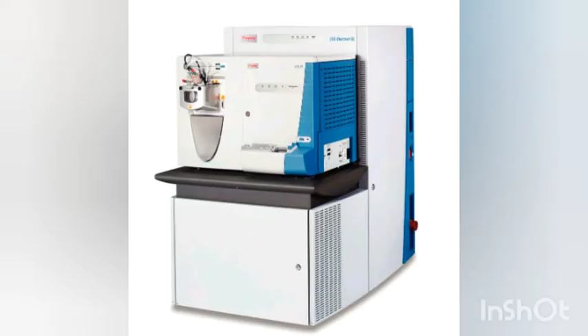Hybrid linear ion trap Orbitrap mass spectrometry. The hybrid linear trap Orbitrap MS, which combines a linear ion trap and a high resolution Orbitrap, is one of the tandem mass spectrometers. The LIT uses a set of quadrupole rods to confine ions radially and a static electrical potential on the end electrodes to confine the ions axially. The Orbitrap consists of an axially symmetrical mass analyzer and makes ions move in an orbital motion around the spindle. Then the image current is detected and converted to a mass spectrum by a Fourier transform. This hybrid mass spectrometer is widely used in proteomics and metabolomics analysis.